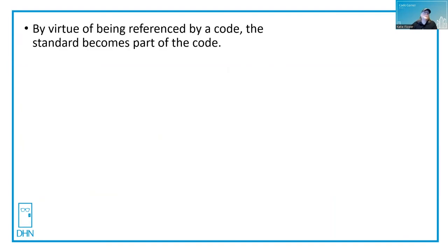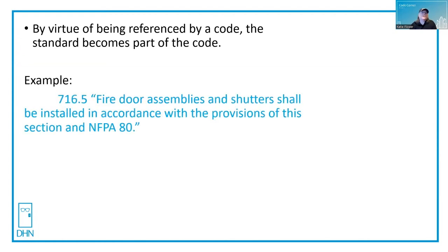By virtue of being referenced by the code, the standard then becomes part of the code. For example, in the International Building Code, Chapter 7, section 716.5 says fire door assemblies and shutters shall be installed in accordance with the provisions of this section and NFPA 80.